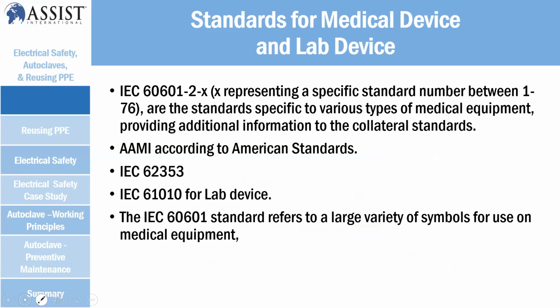To make sure that the leakage current and all these are in the range of safety, there are standards that you need to follow. IEC 60601 normally applies to medical device manufacturing. All the medical equipment that is manufactured has to follow this standard. Then AAMI is according to the American standard. And IEC 62353, when you do servicing, you can follow this standard. And for lab devices, there's IEC 61010, the lab device standard. So you have to follow that standard when you do electrical tests.